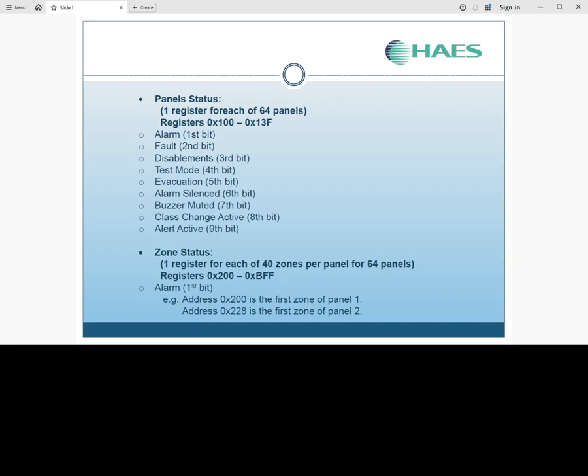Lastly, the zone status. There's 1 register for each of the 40 zones per panel for 64 panels. Registers 0x200 to 0xBFF. The alarm is the first bit, e.g. address 0x200 is the first zone of panel 1, and address 0x228 is the first zone of panel 2.